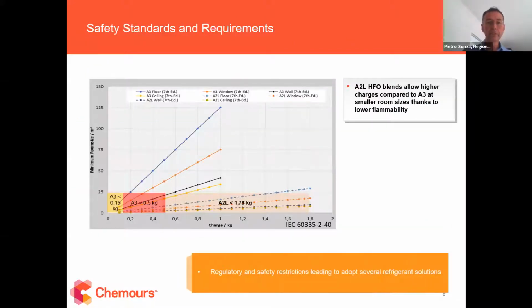Now, safety standards are obviously regulating heat pumps, both from the equipment manufacturing perspective and from the installation perspective. The latter is very well covered by one relevant standard, ISO 5149, and the corresponding EN 378, which sets the charge size limits depending on minimum room size in different application scenarios, whether it's a floor installation, window, or wall, depending on the configuration of the room, etc.